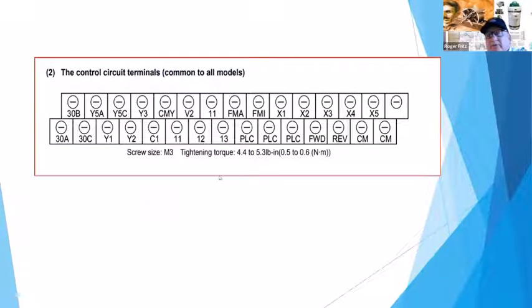So this is an idea, to take the fear out of it. This is the small control board that's normally put on most VFDs, and they're like inputs to a PLC, meaning that it can take various items. The C is the common of an output relay, and you've got 30A, 30B, 30C. Ones are normally closed, ones are normally open. You can select when the functionality of this set of contacts will operate. Then you've got the Y sections. These also have a set of contacts on them, and again you can control when those functionalities operate.